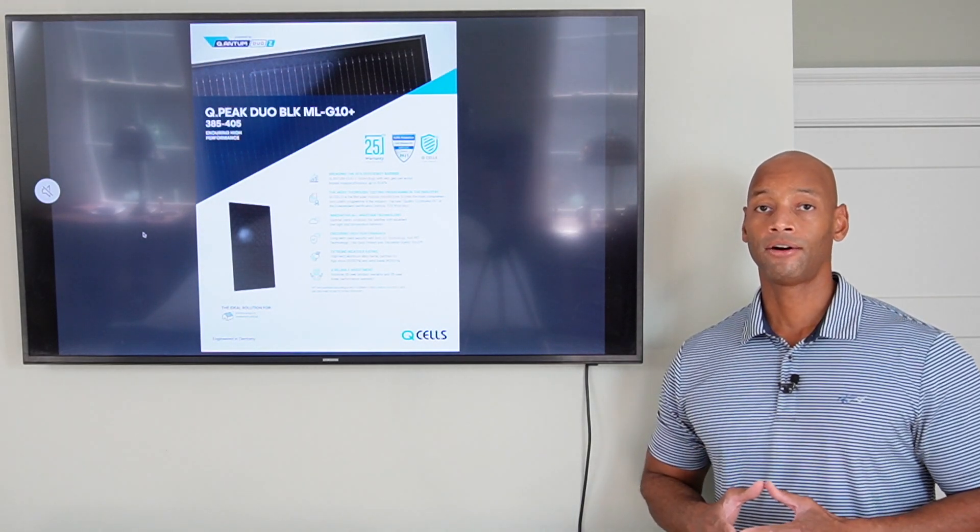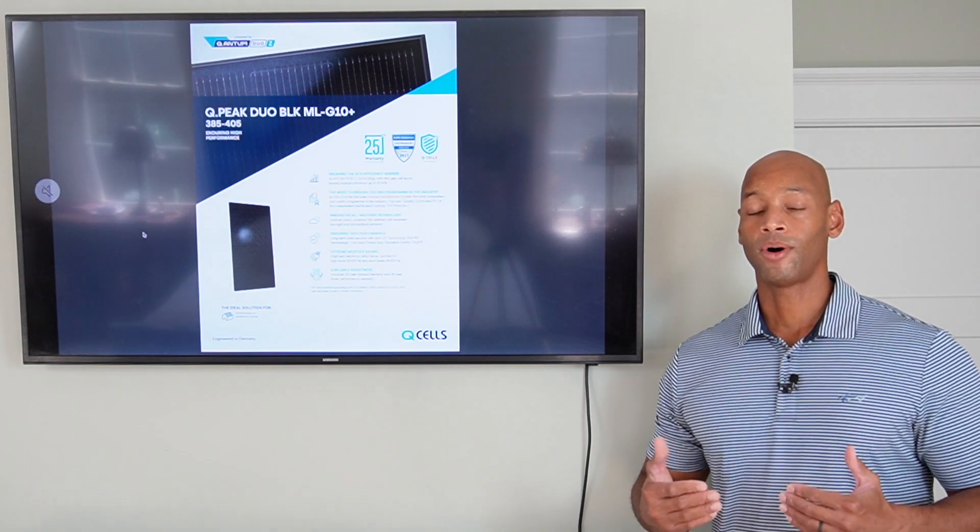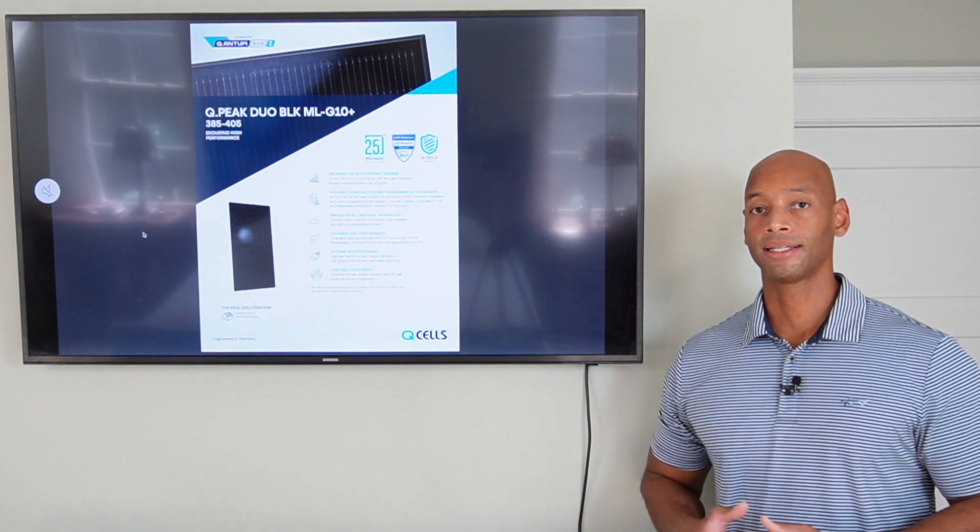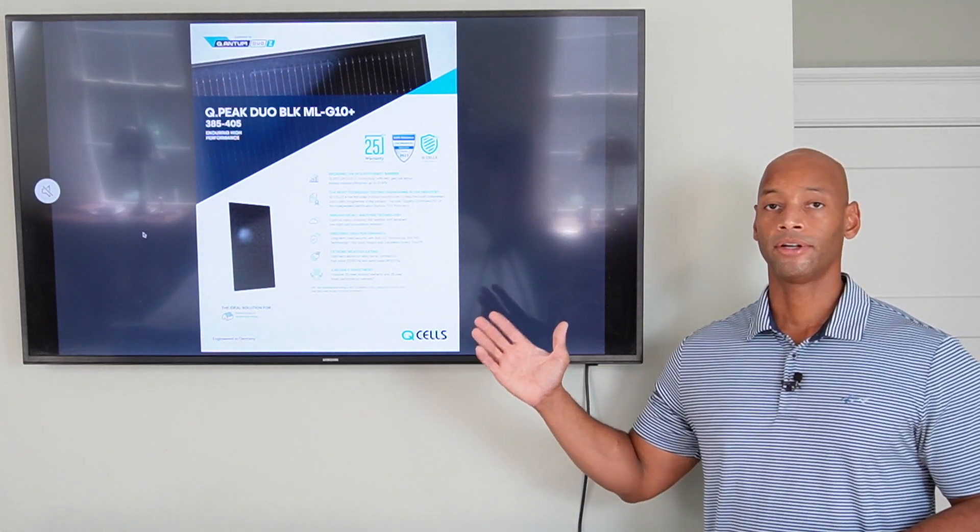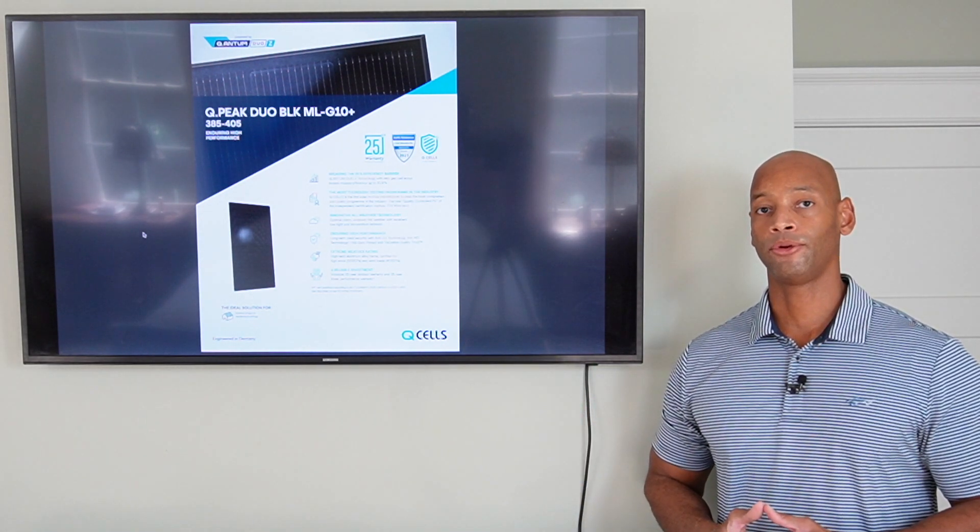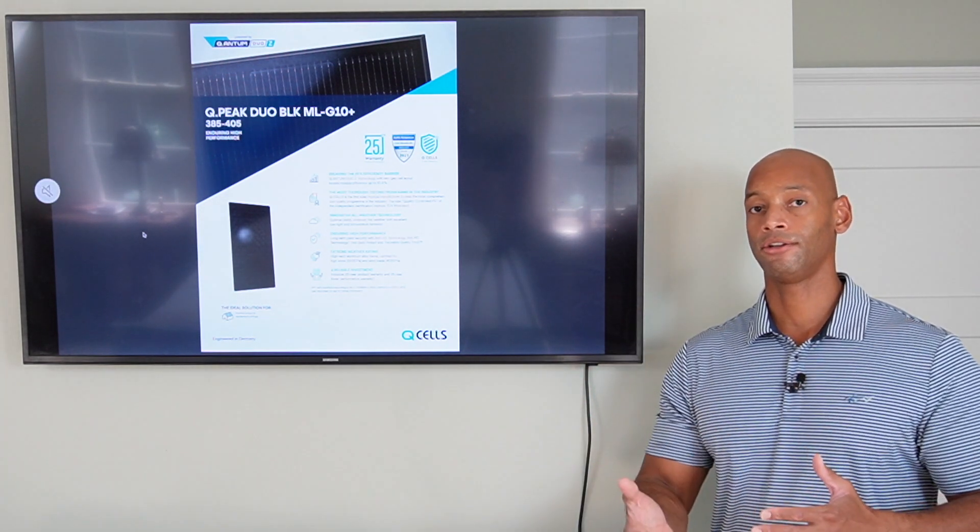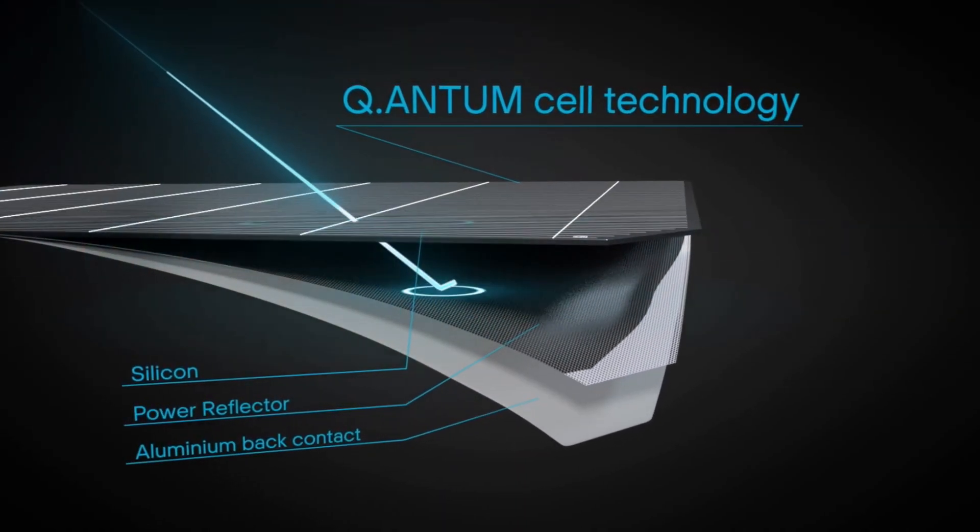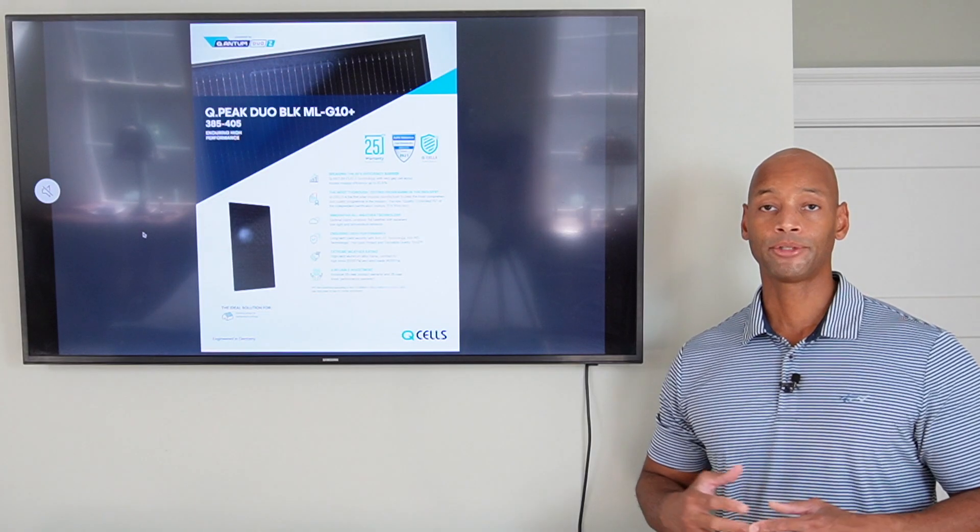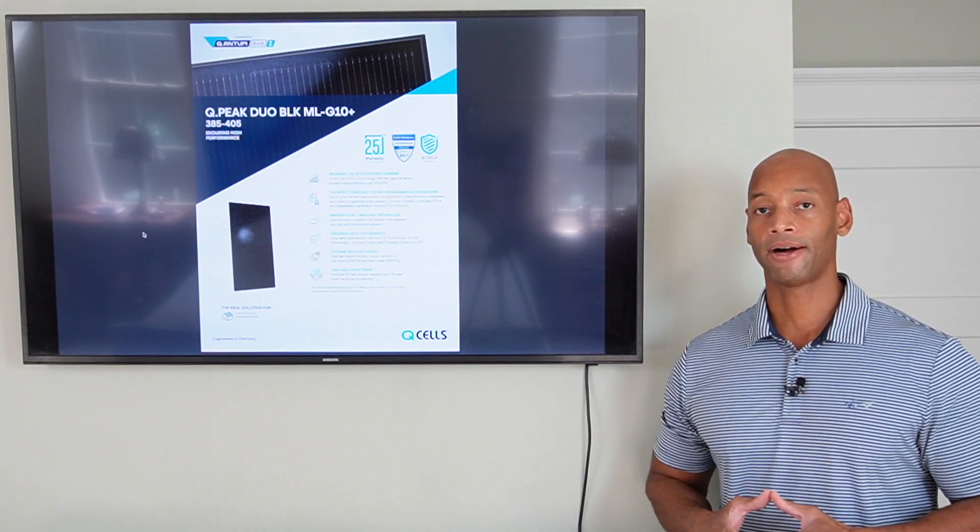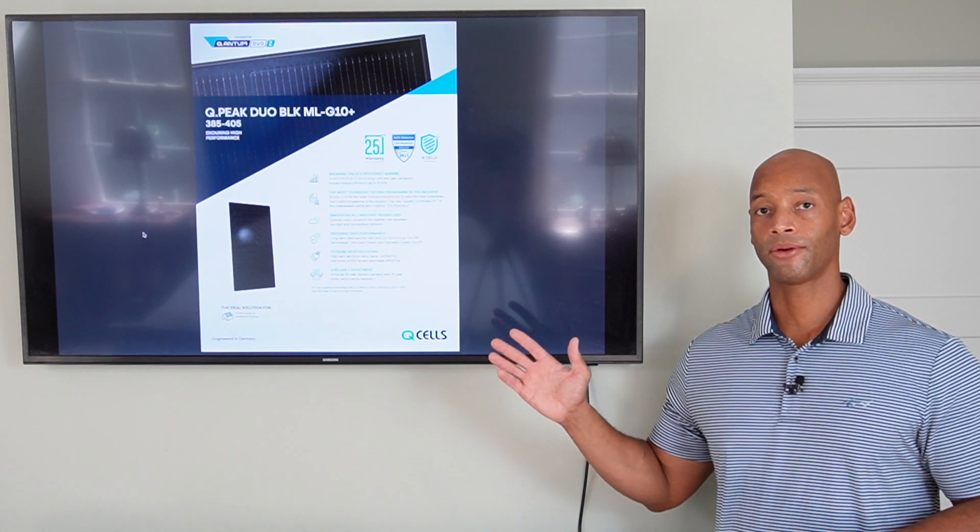The Q-cell G10 also includes the Q-cell's namesake quantum technology. And what the quantum technology refers to is, behind the solar cells, there is a reflective paste that will capture sunlight. Sunlight that normally would have passed straight through the cell and just hit your rooftop. The reflector is able to capture a portion of that and reflect it back out through the front of the cell, capturing about 5% additional power that otherwise would have been lost. So you get the performance benefits of the quantum technology.